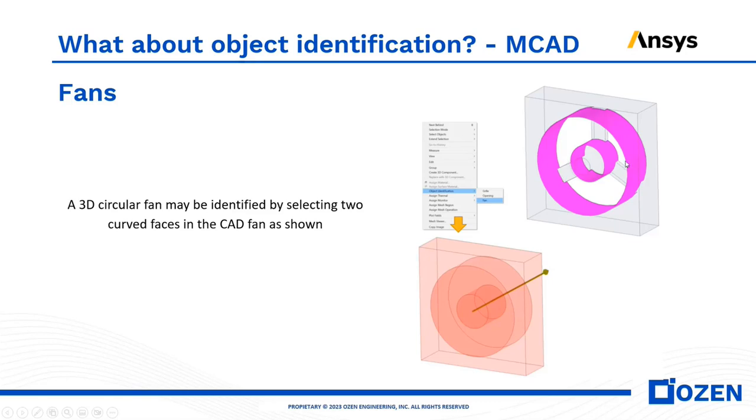And we can even handle this with a multiple reference frame, but it will require a lot of computational resources to solve it. So Icepak can simplify this real fan geometry into a simple fan model, right? And basically what we do, and we can do this inside Icepak, we can also do this inside SpaceClaim, is we select the hub surface, we select the outer case surface, and we tell Icepak or SpaceClaim, hey, I want to model this as a fan in Icepak. So when we select that, immediately this geometry will be converted to something like this. Right here, there are some numerical sources, momentum sources that will resemble or replicate the fan effect over the airflow. So we can now have a fan model, a simplified version, based on a real geometry.